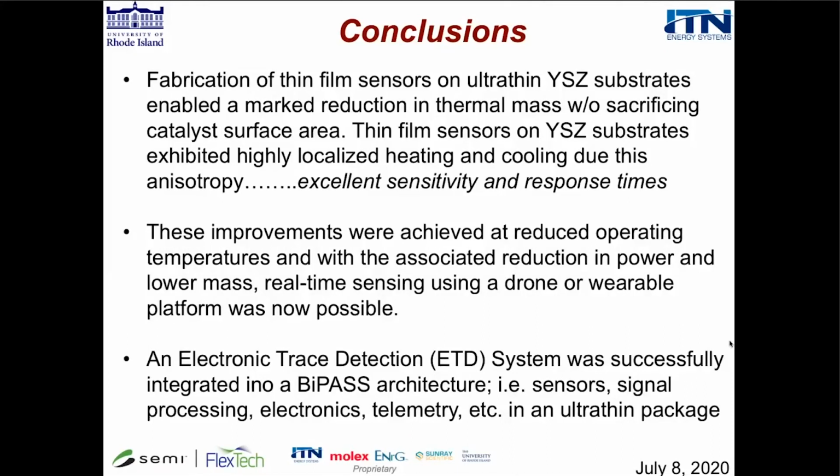5 seconds or so. And we have been testing this whole system in a CT tunnel environment to see if we couldn't scan the area or headspace around luggage in a CT tunnel at the same time the luggage is being x-rayed. And so we think our response times are fast enough that we can capture that information the same time that a package or a piece of luggage would be scanned using x-rays.